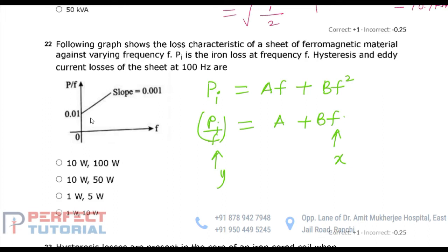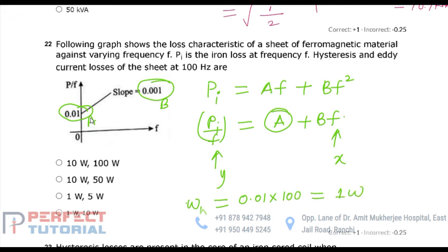ओके, सो यहाँ पर ग्राफ दिया हुआ है Pi by F वर्सेस फ्रीक्वेंसी का. देखिए इंटरसेप्ट आप कैलकुलेट कर लेंगे 0.01 इज द इंटरसेप्ट A एंड स्लोप दिया हुआ है 0.001 इज व्हाट द वैल्यू ऑफ B. सो B का वैल्यू मालूम, A का वैल्यू मालूम, आप डिटरमिन कर सकते हैं hysteresis loss and eddy current loss at 100 Hz. So hysteresis loss WH at 100 Hz is equal to A into 100. A is your 0.01 multiplied by 100 to be equal to 1 watt, and eddy current loss at 100 Hz is equal to B into F square. B value is your 0.001 and F square is your 100 square, meaning 100 into 100 to be your 10 watt. So hysteresis loss is your 1 watt and eddy current loss is your 10 watt.